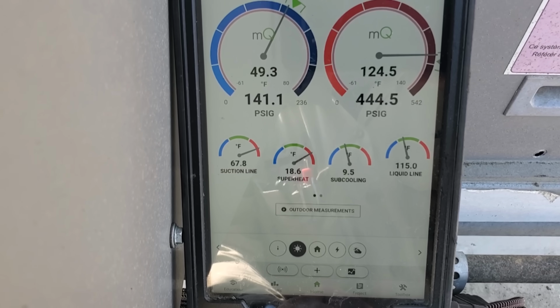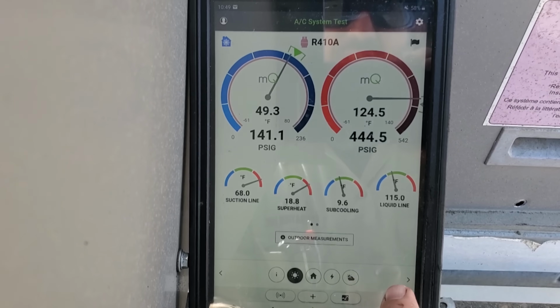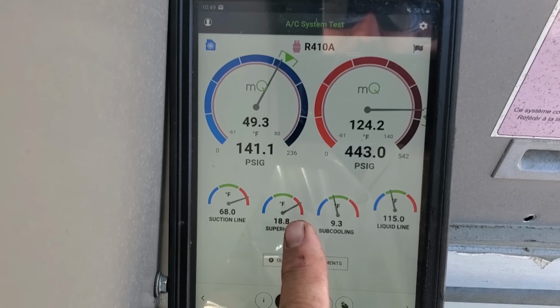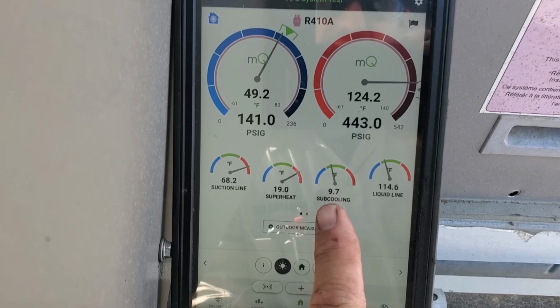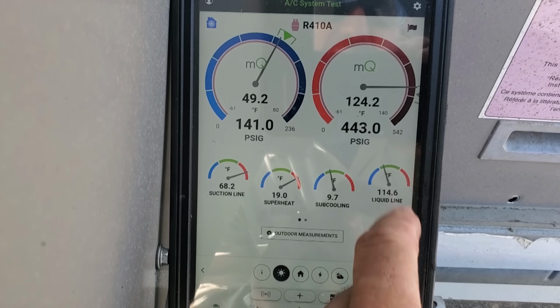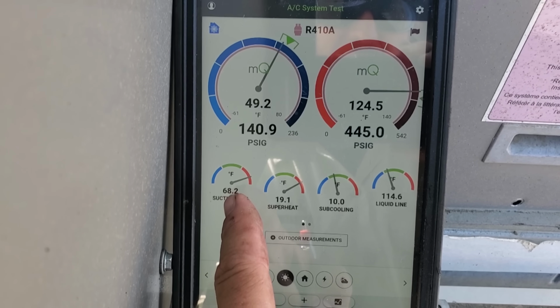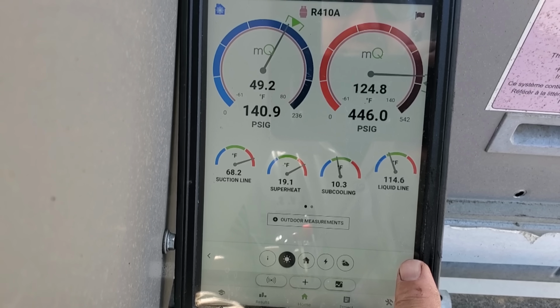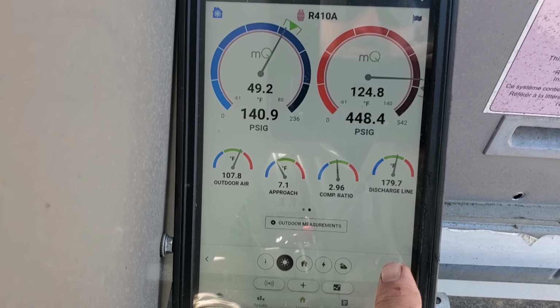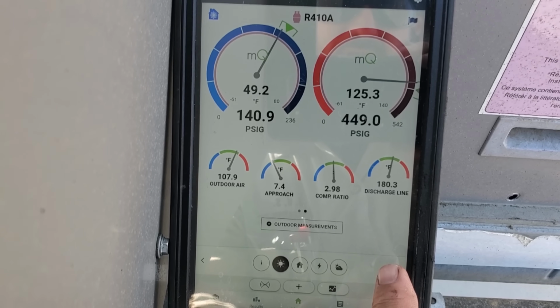All right, so we're using Measure Quick here. And according to Measure Quick, let's go through this. Superheat's just a little bit high. It's not horrendous. Subcooling's doing pretty good. Our pressure targets are somewhat good. Suction line temperature's a little bit high. Let's move on over. Outdoor air temp's about 108.